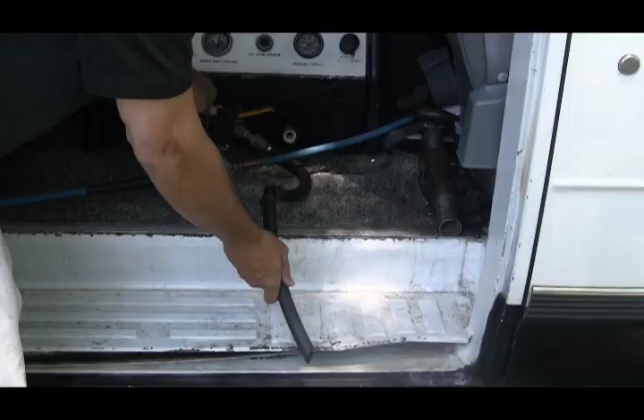On a direct drive like this one, a lot of them have a bleeder valve already built on, so you can pull it off. But to me that's kind of tacky to do in a customer's driveway. So what I do is hook up my little bleeder hose, and you can run it into your vacuum hose port, or lift it up and run it into your 5-gallon mix tank. Fill it up, cool it off, and get it down to the desired temperature. That's how I handle direct drives.